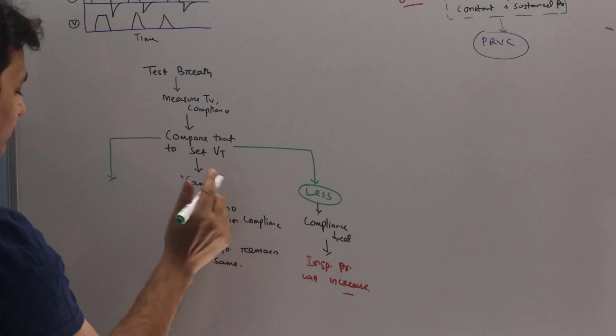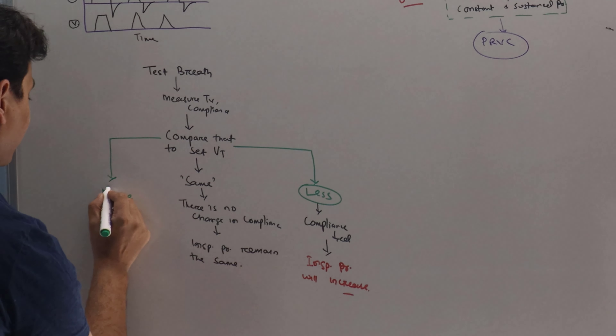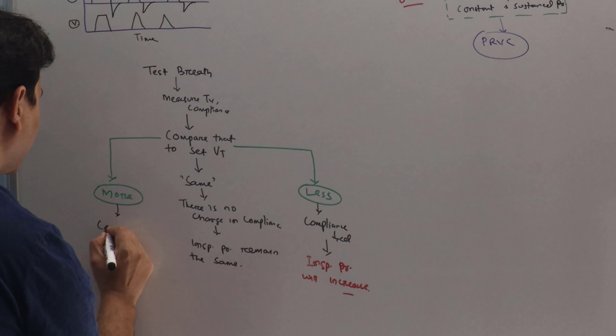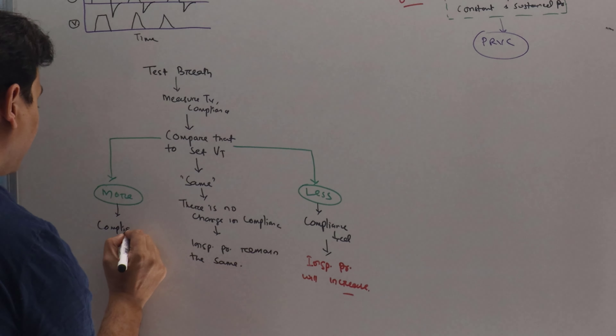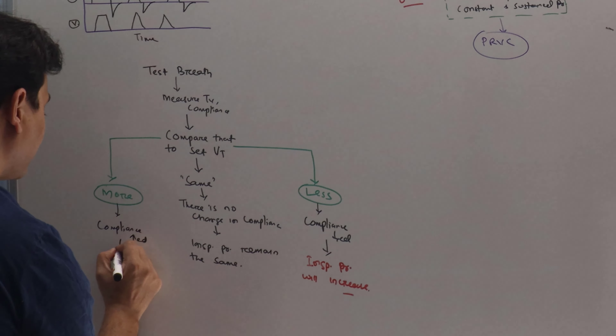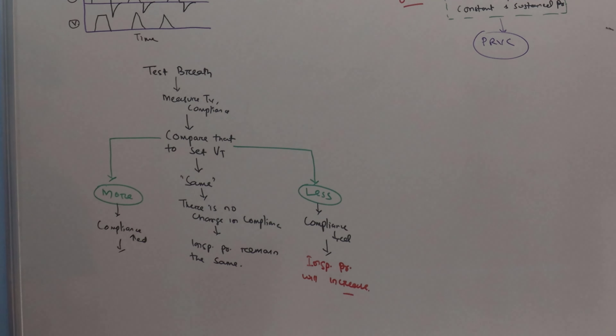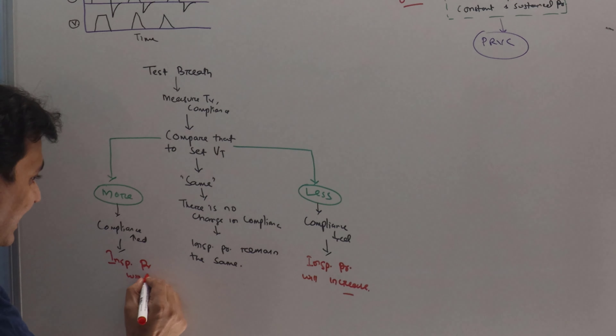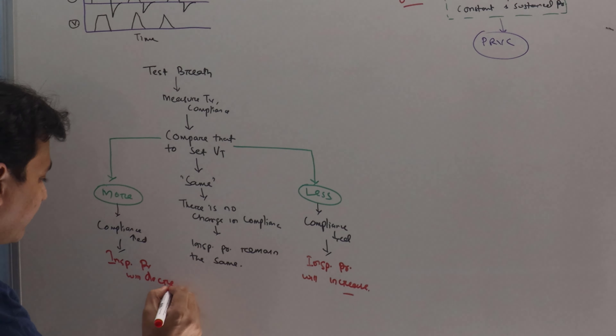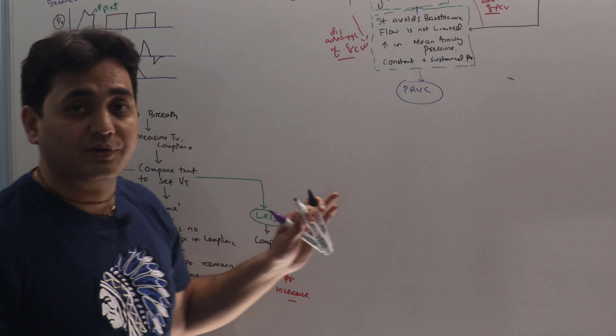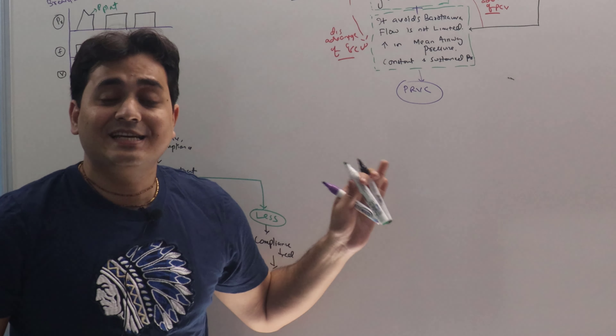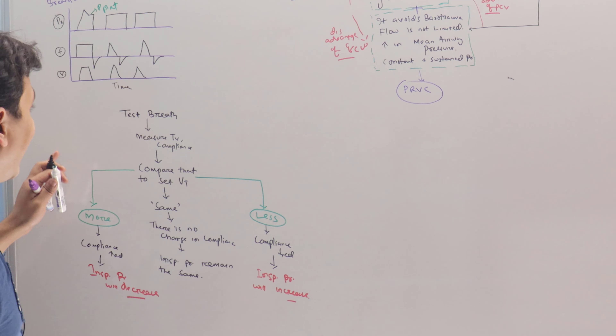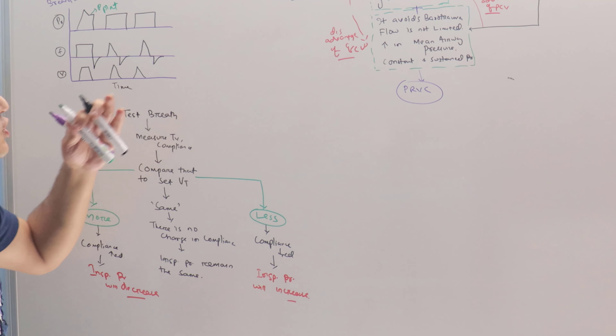If the measured tidal volume becomes more than the set tidal volume, that means compliance has increased. In this situation, the inspiratory pressure will decrease. You can see how it is very dynamic, responding to changes in tidal volume and changes in the compliance of the lung parenchyma. This is the advantage of this kind of adaptive mode of ventilation.